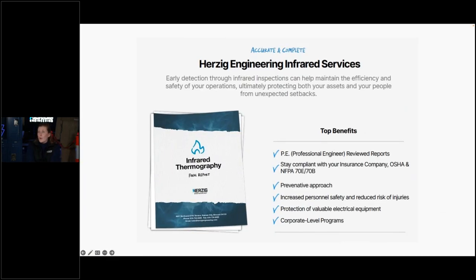We're almost up on time here, so I just want to throw out that yes, we can do infrared scanning. We can look at your equipment and provide a preventative approach for avoiding these equipment failures, which helps avoid arc flash and shock events, electrical fires, and unexpected downtime. There's too many positive reasons to do it, it's kind of a no-brainer. Making sure that you have that completed is very important. Whether we do it or you get a camera for yourself, that's fine. Just make sure it's someone who knows what they're doing so you get the most out of it.